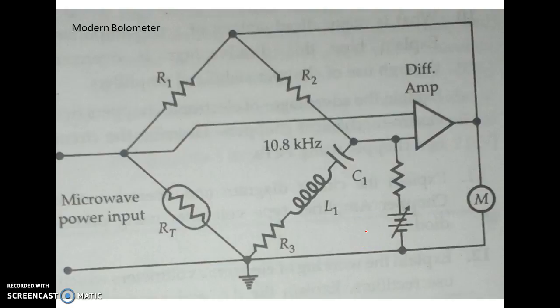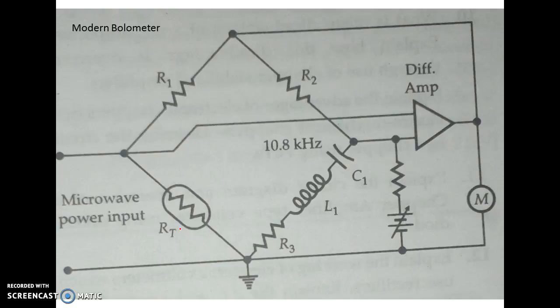To sum up: for low power measurements less than 10 milliwatts, you can use bolometers. For powers in the range of 10 milliwatts to 10 watts, you can use the comparison or flow calorimeter. For powers greater than 10 watts, you can use the calorimeter power meters. This covers all the power measurement methods at RF frequencies.